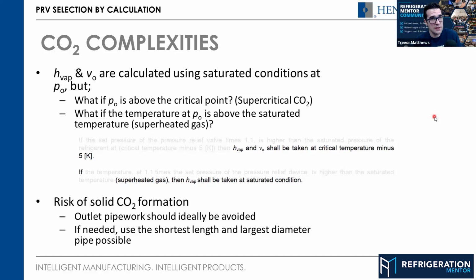This is something that still is a gray area that is not pointed out in the code. And I'm sure this is the case in other parts of the world as well. It's kind of gray, and depending on the inspector you get, they may approve or disapprove the installation of those PRVs. We know one thing: we cannot have a shutoff valve before any pressure relief. And I know we didn't get into it yet. You cannot do that, because if someone forgets it shut off or something like that, an accident could happen. And then you've got a ticking time bomb potentially.